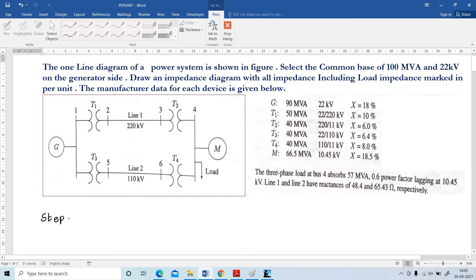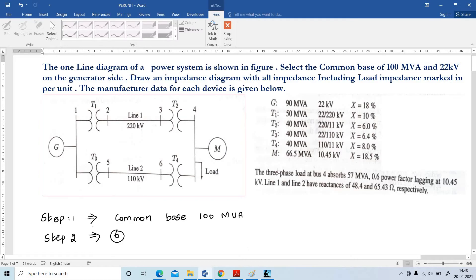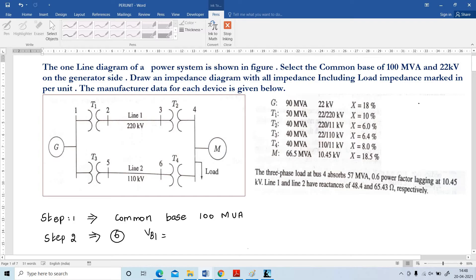Step number 1: Common base is 100 MVA. Step number 2: Voltage bases must be determined for all sections of the network. There are totally 6 sections. VB1 is given on the generator side as 22 kV.